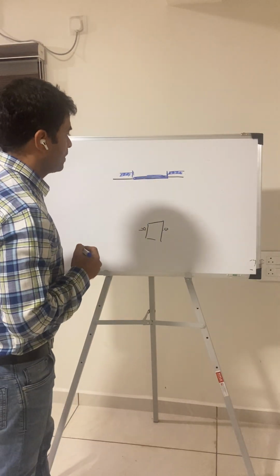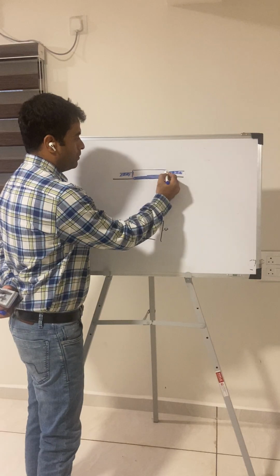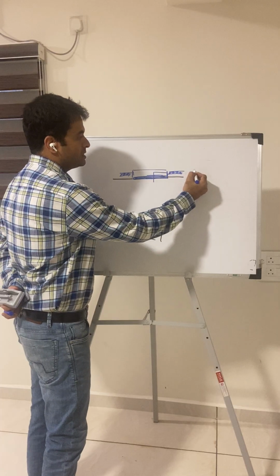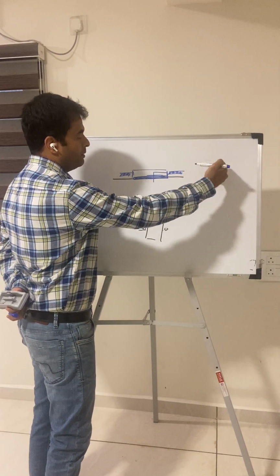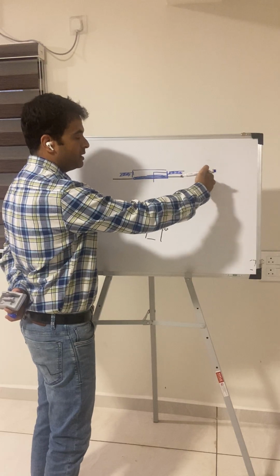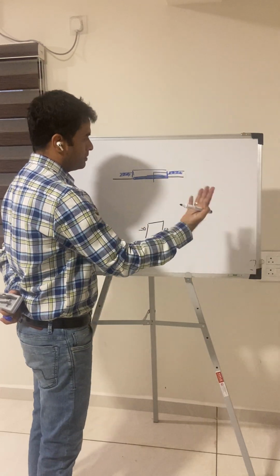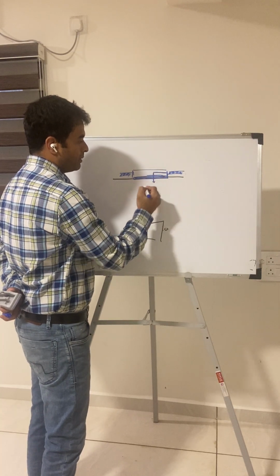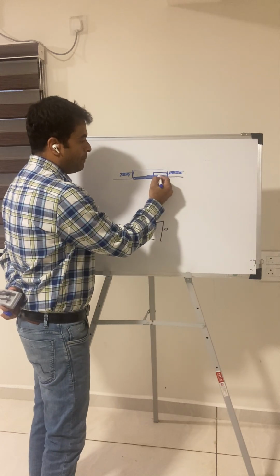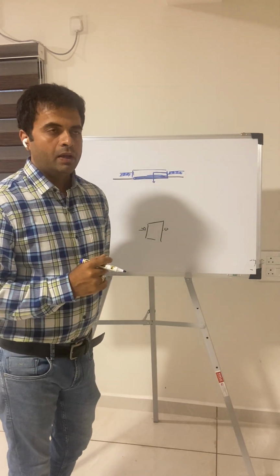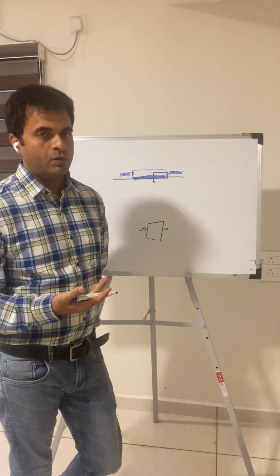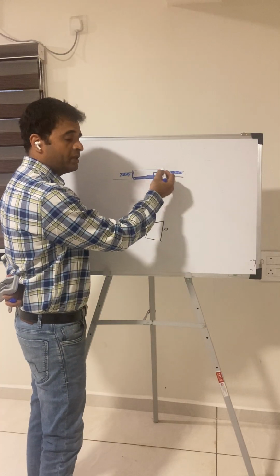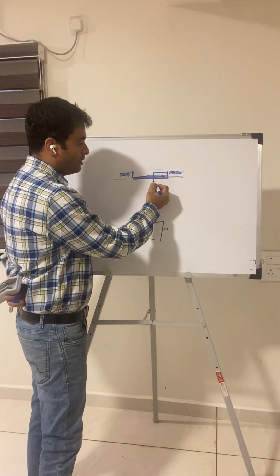0.3 micron. So now the airflow from here gets filtered. I will tell you about the process behind this and the previous process in the next video or some other time. Now air comes from here, filters through the HEPA module and comes back. The HEPA module will have some static pressure, initially around 25 mm of water column. So air comes from this side, passes through the HEPA filter with pressure, gets filtered and comes into your OT.